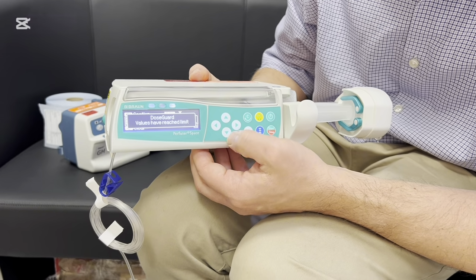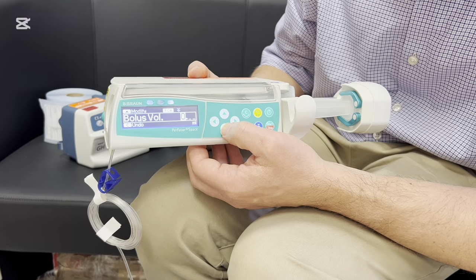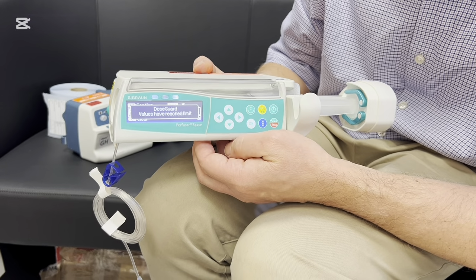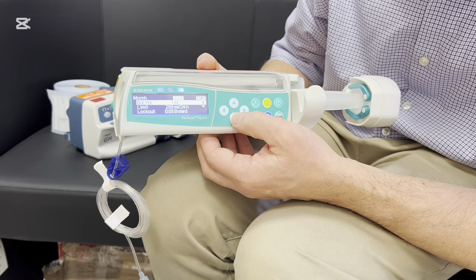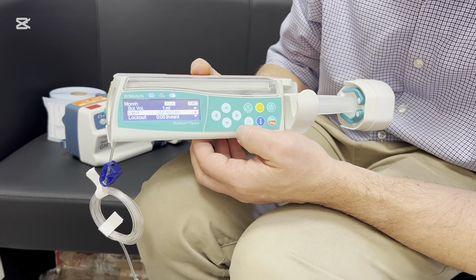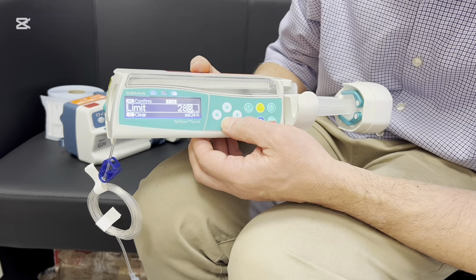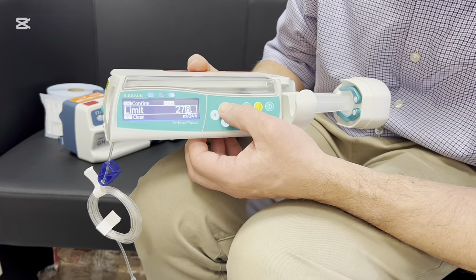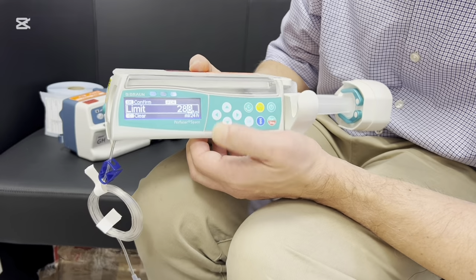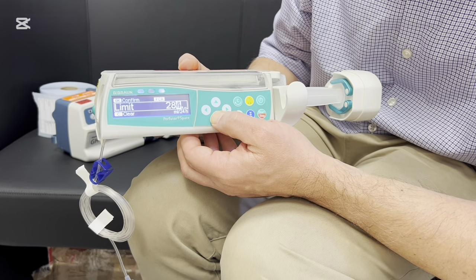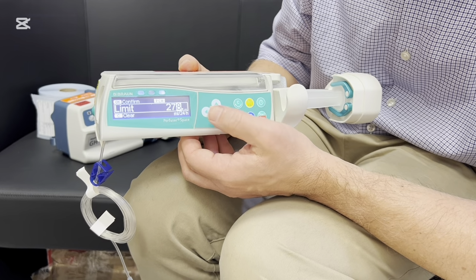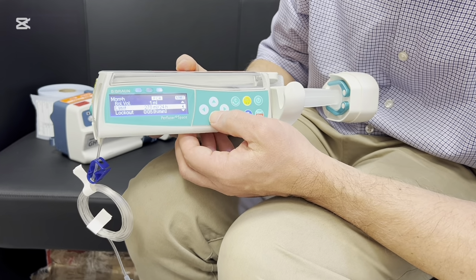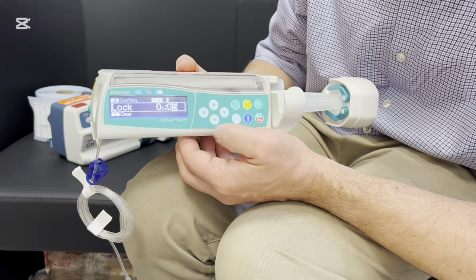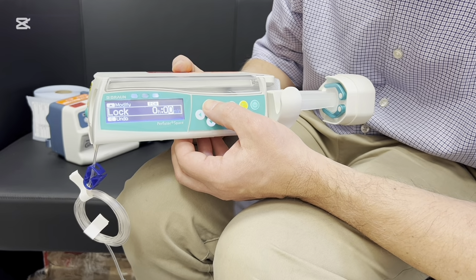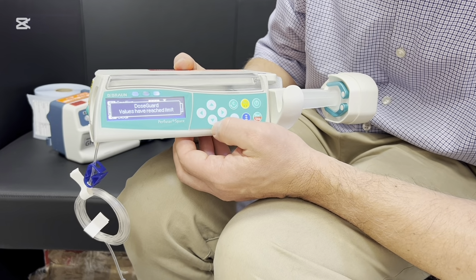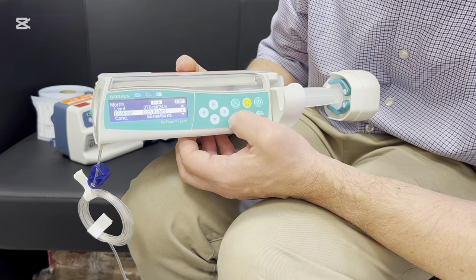Can we change it? No, you can't change it. It goes against the guardrails. You can change it to 0, you can change it to 1, but it will not allow you to increase it to any more than 1 mil. So we're pressing OK on that. It's going to limit you to 288 mils in 24 hours. Can we reduce that? We can certainly reduce it. Can we increase it? You can't increase it to any more than that. So we'll press OK on that. The default is a 5-minute lockout. I suspect it won't allow you to give any less than a 5-minute lockout, or any more than a 5-minute lockout. So press OK for a 5-minute lockout.